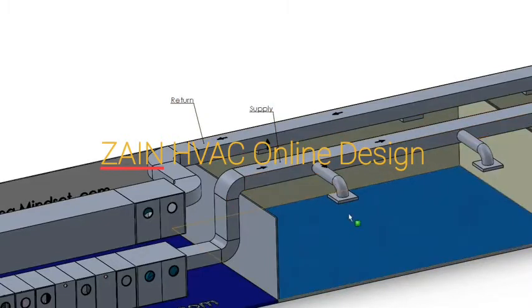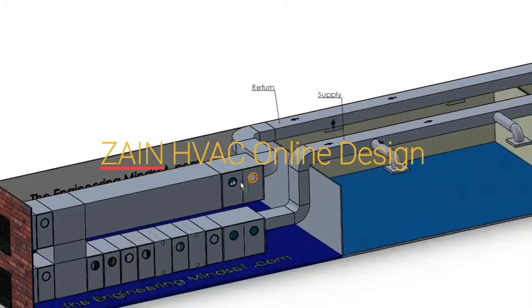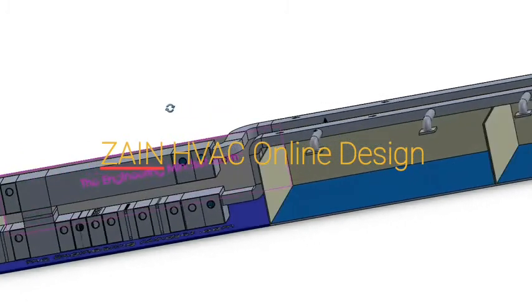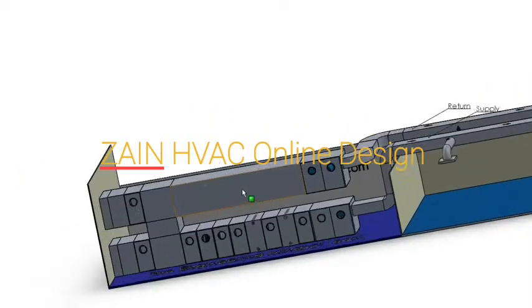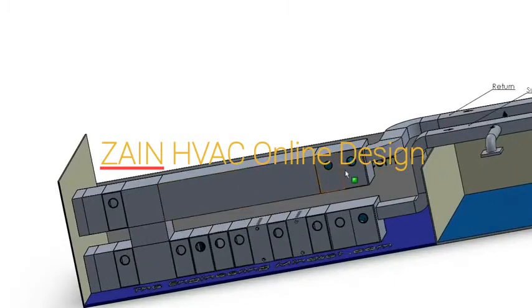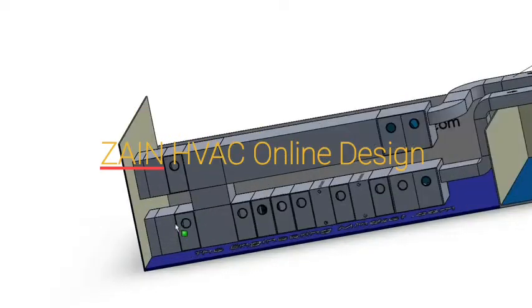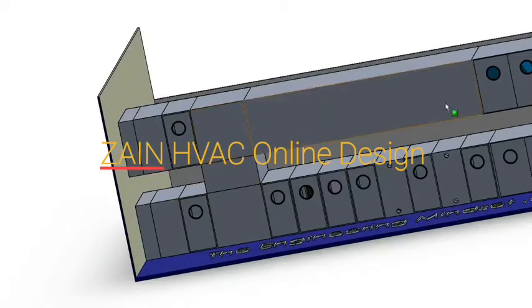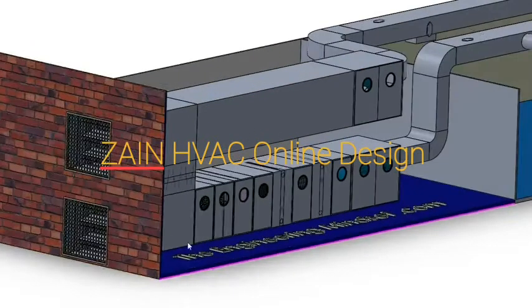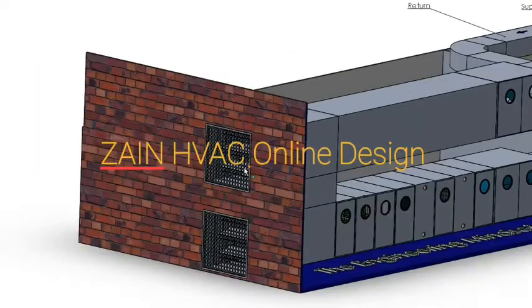So all that air is going in, pushing into this room, circulating around, conditioning it, and then it's entering back into the return duct, and that makes its way back into the return side of the AHU. And there is also a fan in this one which is sucking that air in, and that's blowing that into the main chamber and then off. And then we'll look at it later, but there's some dampers in here, and that will control how much of that air recirculates and how much of that goes back and is rejected out of the vent here into the atmosphere.